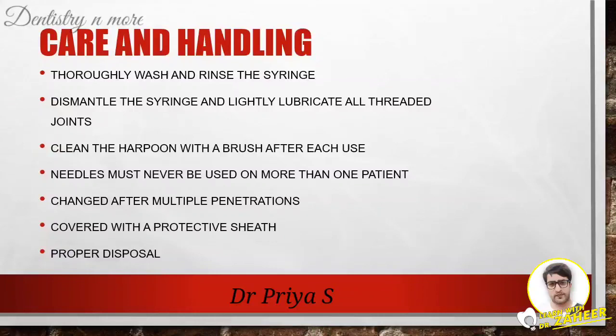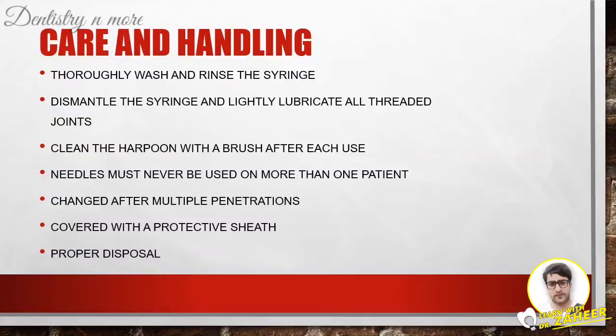To carefully handle the local anesthetic armamentarium: after each use, thoroughly wash and rinse the syringe free of local anesthetic solution, saliva, or any foreign matter. The syringe may be autoclaved like other surgical instruments; after every five autoclavings, dismantle the syringe and lightly lubricate all threaded joints, especially where the piston contacts the thumb ring. Clean the harpoon with a brush after every use. Needles must never be used on more than one patient, should be changed after three or four tissue penetrations in the same patient, kept covered when not in use, and properly disposed of after every use.